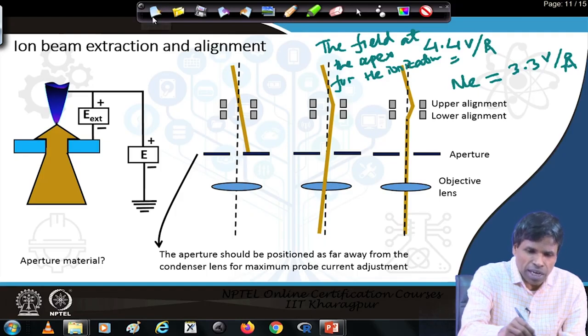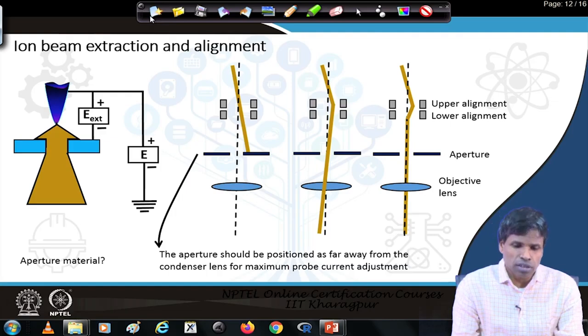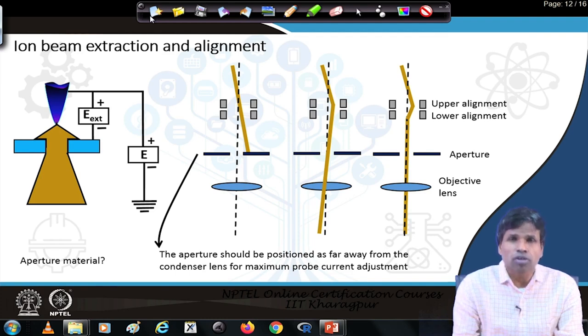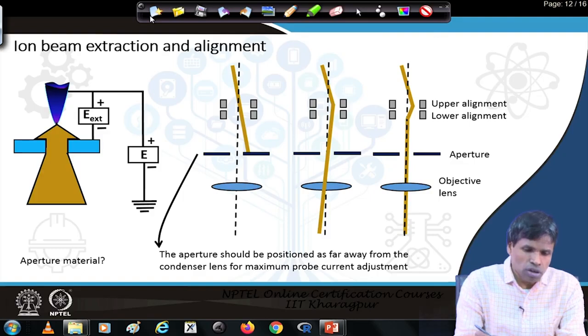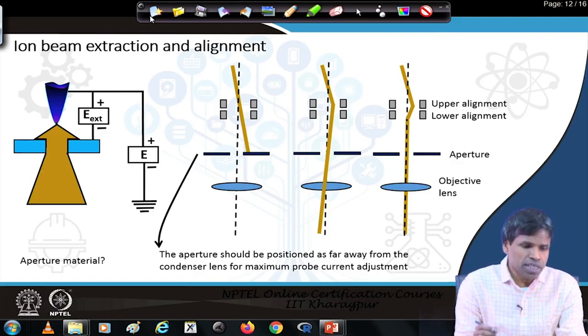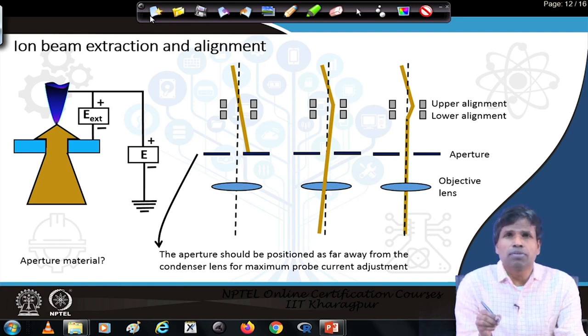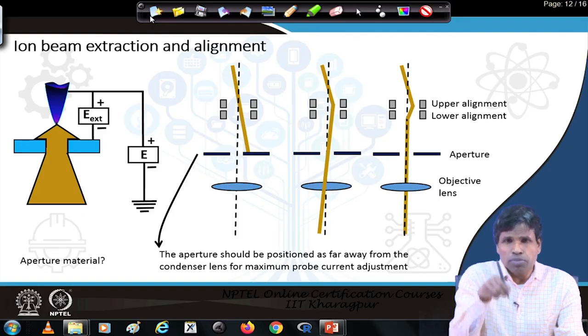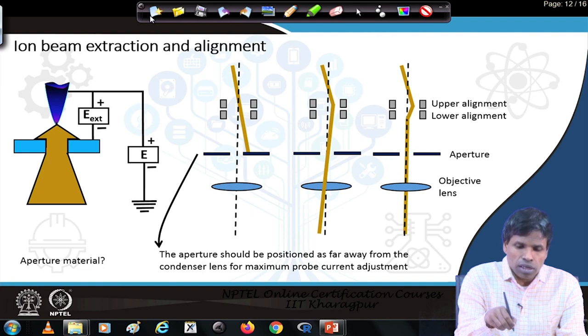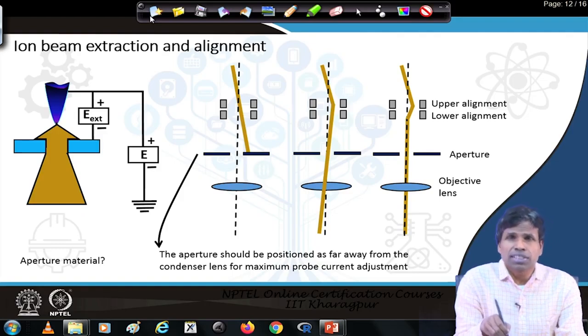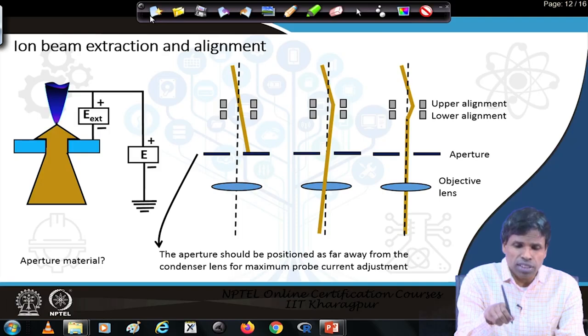Once the ion beam is generated by applying the optimum potential, it must be aligned so that it comes downwards along the optic axis and reaches the condenser lens. First, alignment is done mechanically by tilting or shifting. We have 3 atoms providing 3 beamlets, but we need only 1 beamlet. So the tip is tilted so that one atom's beam comes downwards through the column, and this mechanical tilting and shifting is done so that the beamlet comes straight downwards.